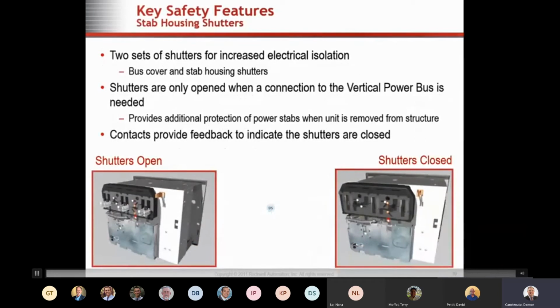So how does this work? It's got two sets of shutters. When you operate the quarter-inch hex key device in the front, it removes the power from the stabs from the vertical bus, and when they are removed, two shutters will close.